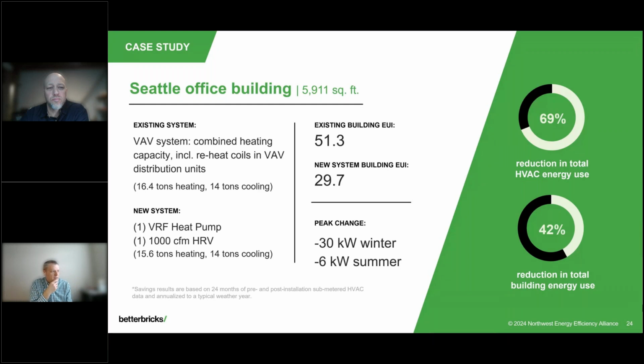So on this building, this is about a 6,000 square foot building. I think when we look at these next 3 slides, the key things to take a look at are the EUI differences, and then also to look at the sizing on each of these systems. So the existing building had a VAV system with a combined heating capacity, including reheat coils in the VAV unit. So it had 16.4 tons of heating and 14 tons of cooling. It went to 1 VRF heat pump, 1,000 CFM HRV, reduced the heating load a little bit, kept the cooling load the same, but we went from an EUI of 51 to an EUI of just under 30, right? And then the other thing about this one that was really nice is it had peak energy savings that were reduced in the winter and the summer by a good number, right?